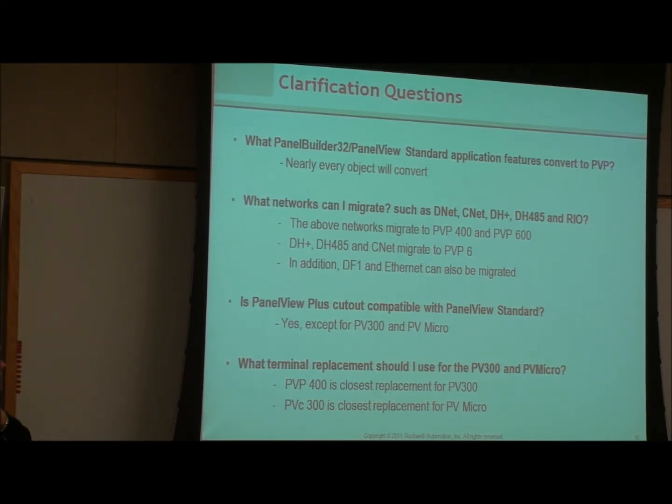Just some clarification: most Panel Builder 32 and PanelView Standard objects convert — nearly every one of them — because RSView Machine Edition was based on Panel Builder 32. The communication protocols DeviceNet, ControlNet, DH Plus, DH485, and Remote IO can all migrate to a 400 or 600.